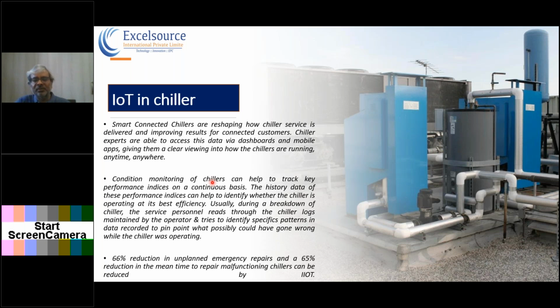This will help us identify the optimum efficiency of the evaporator and condensers, which in turn determines the amount of energy used. If there is no fouling in the condenser and no fouling in the evaporator, on the water side, the cooling media side, the chiller will consume a low amount of power, because we will be able to operate the same chiller at lower power. The kW per TR is going to be much lower than it is designed for, because normally we consider some fouling factor while selecting the heat exchangers, I mean the condenser and the evaporators. That is the worst condition of the plant. So if we monitor the temperatures in and out of the condensers and evaporators thoroughly, we will be able to operate the chiller at optimum kW per TR, and the energy can be saved.